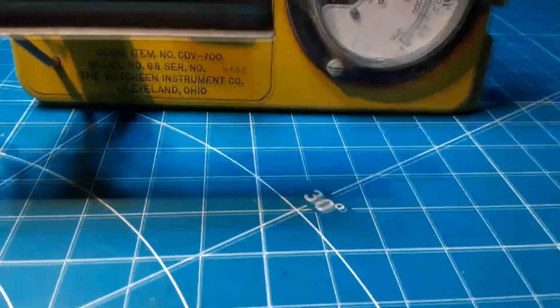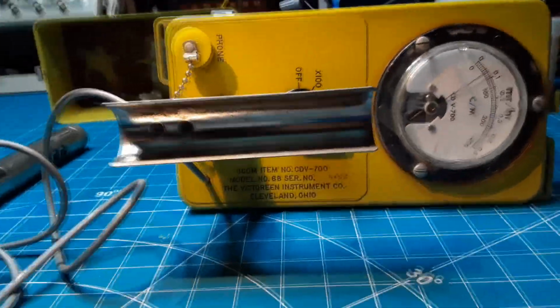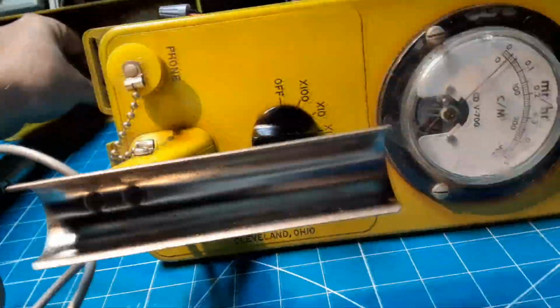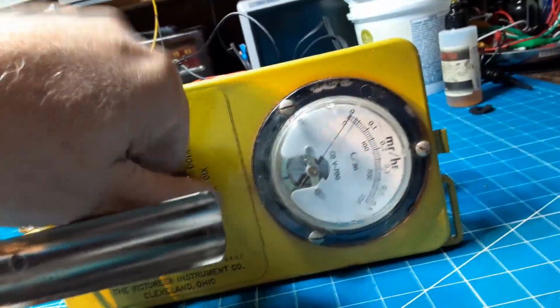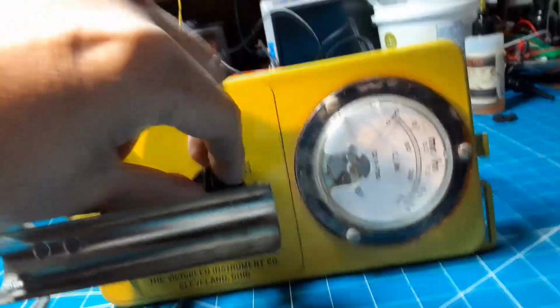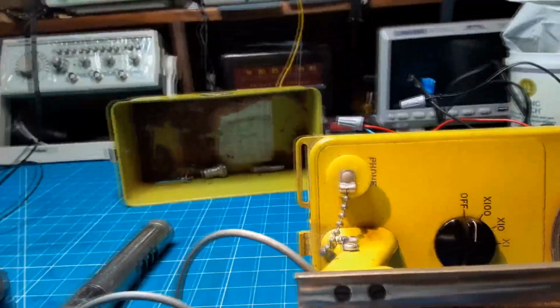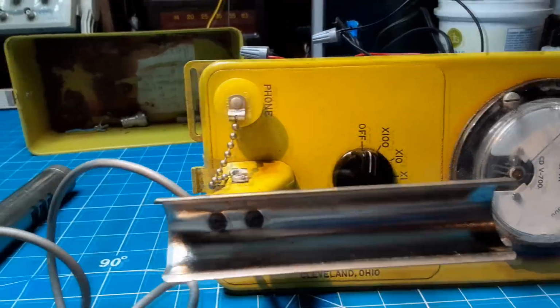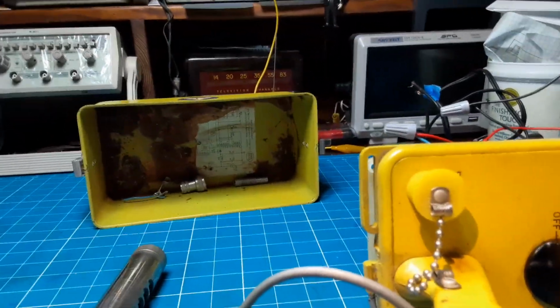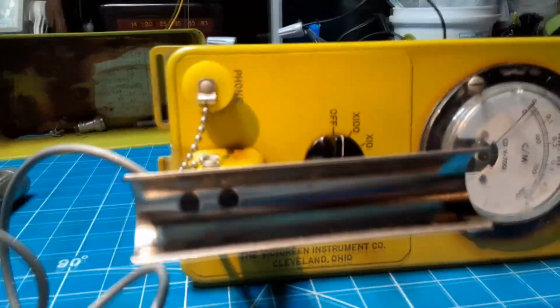Sorry about the people walking around upstairs, but maybe you can hear that. So that was the problem. That transformer let go. And of course the clip let go and the batteries corroded and all of that. So I'm going to shut this off, and I will let it discharge while I work on that, and then I'll discharge it manually, check that capacitor, and the next thing would be to calibrate it.